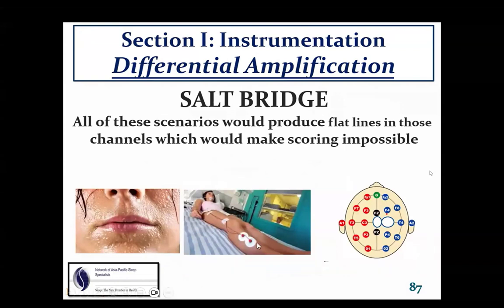In all of these scenarios, in sweat, in instances where we have our electrodes too close together, and in instances where we've had cream extend between two electrodes, all of these scenarios would produce flat lines in those channels, which would make scoring impossible. And let me also say, impedance will be normal. It'll look great, but when you go to record, differential amplification is going to cause a flat line.